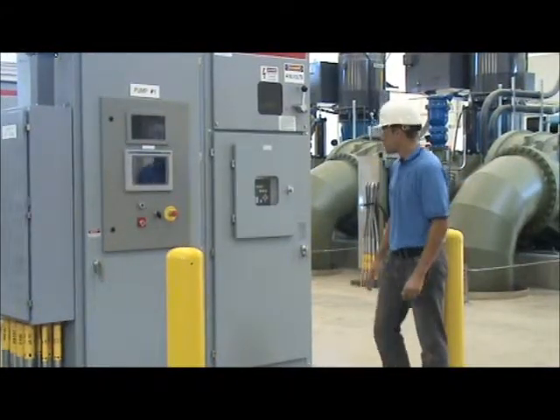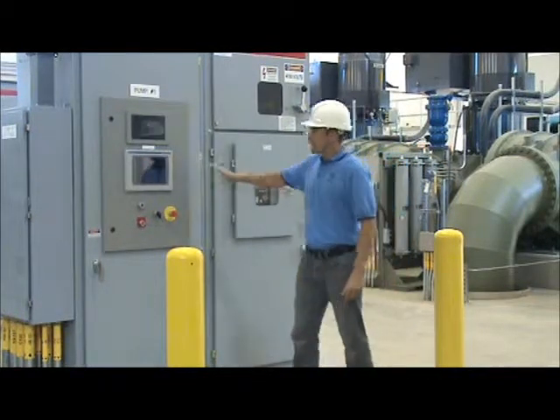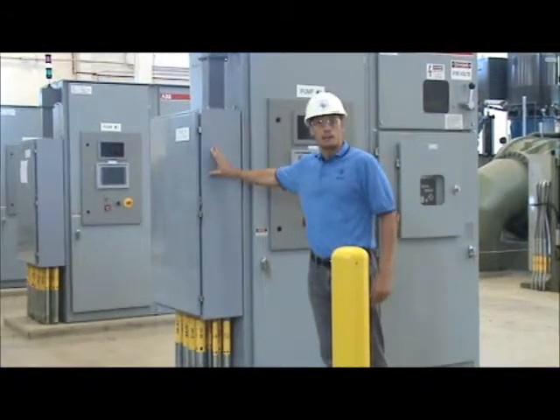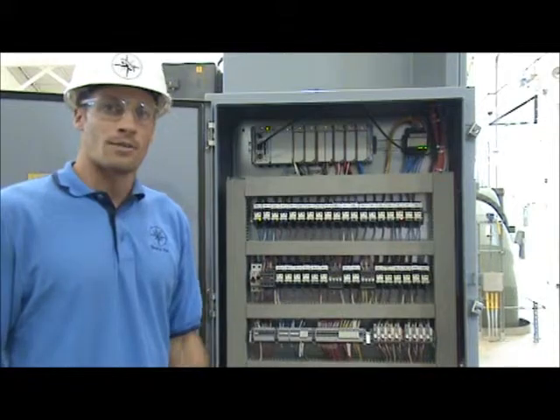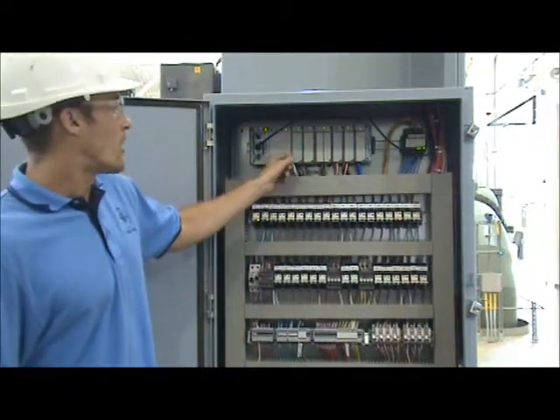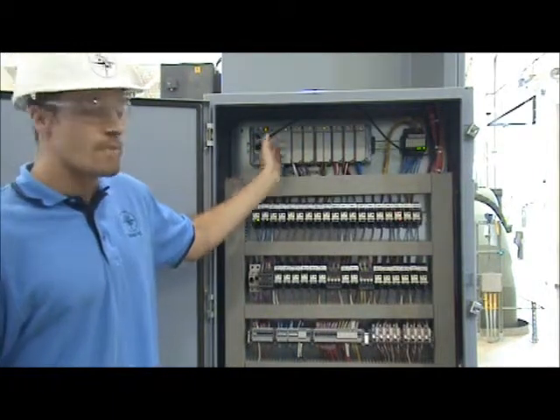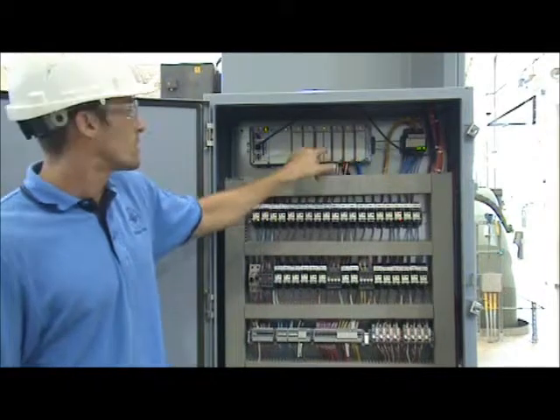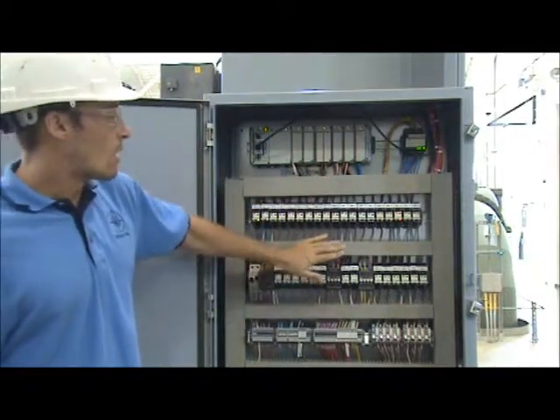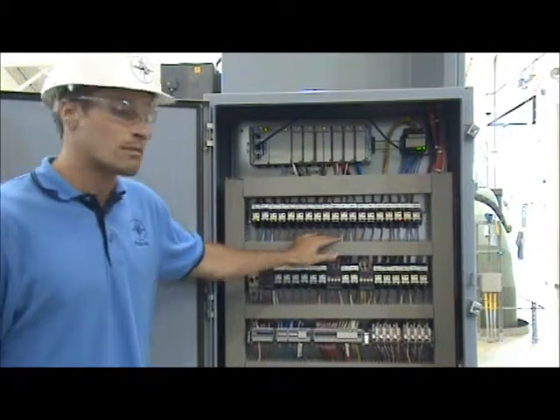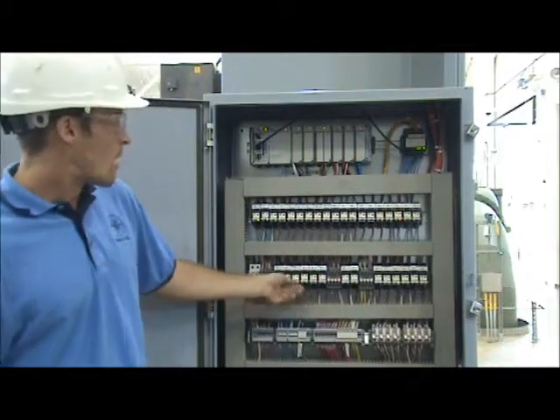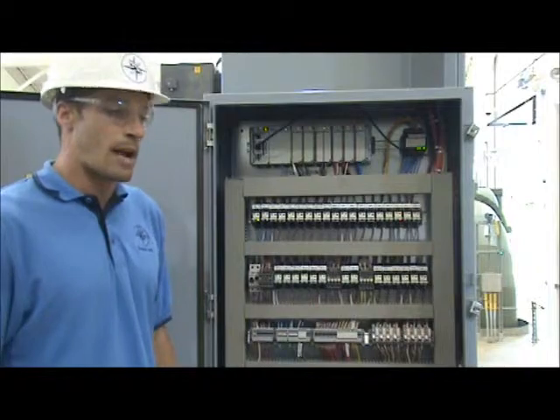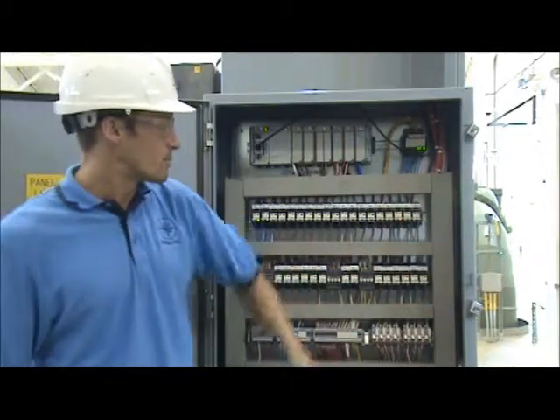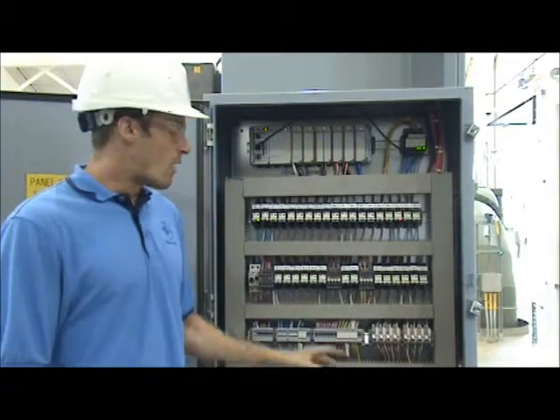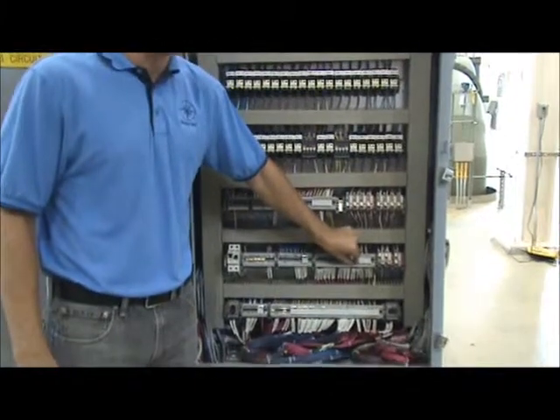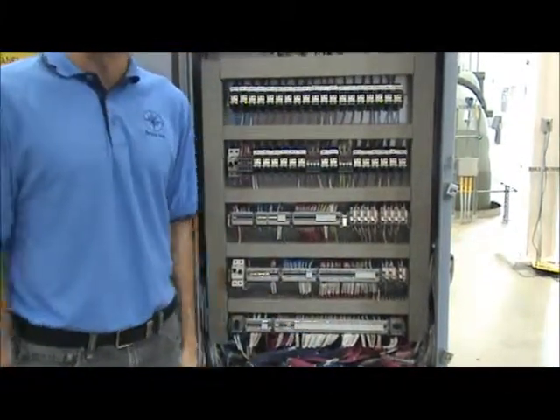The 3 low voltage compartments include the soft start control panel, the HMI panel, and then the PLC and relay panel. Mounted on the left side of our soft start panel is our main control panel, which houses our Allen Bradley CompactLogix PLC with Ethernet capability, our digital inputs and outputs, then our analog inputs and outputs. And then all of our interfacing goes through interposing relays. We chose the Schneider brand for the ease of wiring, the locking tab, which locks it into its activated position, and then all these tabs, which give a nice display and are easy to read. And then all field connections go to switchblade terminal blocks, so we can isolate signals if need be.